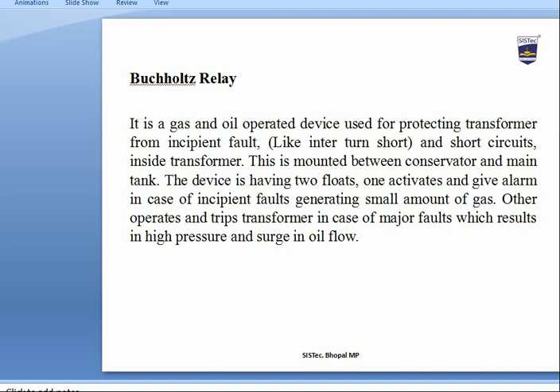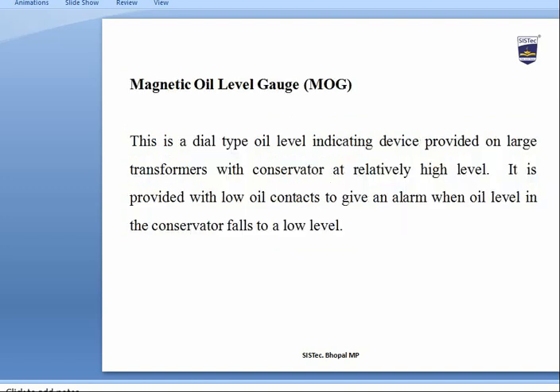The Buchholz relay is a gas and oil operated device used for protecting the transformer from incipient faults — internal faults and short circuits inside the transformer. It is mounted between the conservator and main tank. It has two floats: one activates an alarm for incipient internal faults generating a small amount of gas, and the other trips the transformer in case of major faults resulting in high pressure and surge in oil flow.